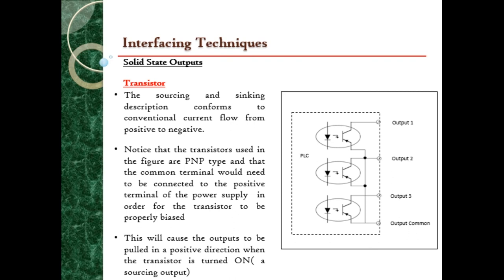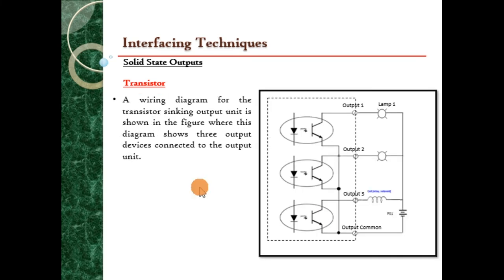So notice that the transistors used in the figure are PNP type, and the common terminal would need to be connected to the positive terminal of the power supply in order for the transistor to be properly biased. This will cause the outputs to be pulled in a positive direction when the transistor is turned on. So this output will be pulled to the positive direction. That's why it is called a sourcing output. While for the sinking output, the current will flow to the common ground here. That's why it is called a sinking output.